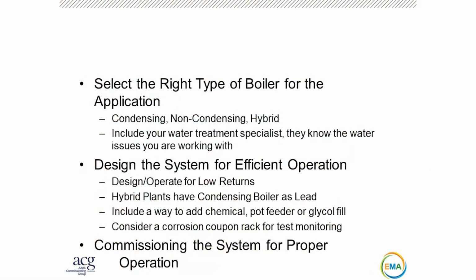So generally, we don't like to put glycol in boilers. Especially, we don't ever want to put them in a steam boiler. But in a hot water boiler, we generally don't put it in there. But if you do, be very careful that you maintain the glycol properly. All right, so just to kind of sum everything up here. So, it all really comes down to picking the right boiler, the right application, condensing, non-condensing, figure out the water treatment, talk to the people you're working with, get everybody on the same page.